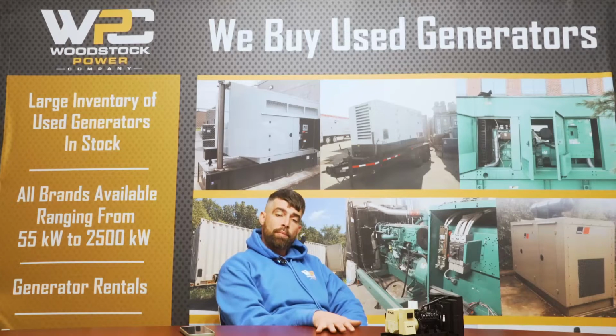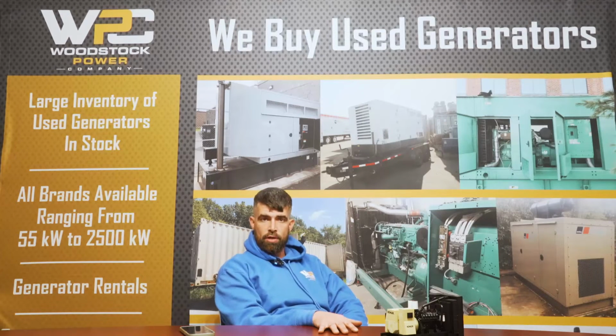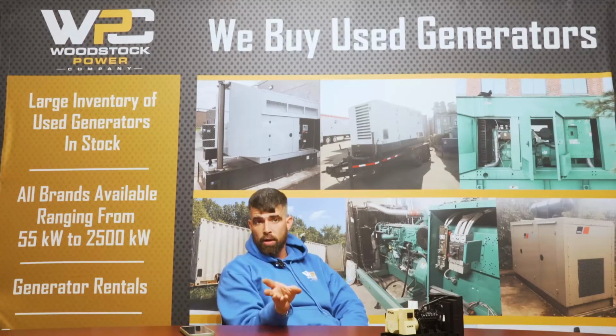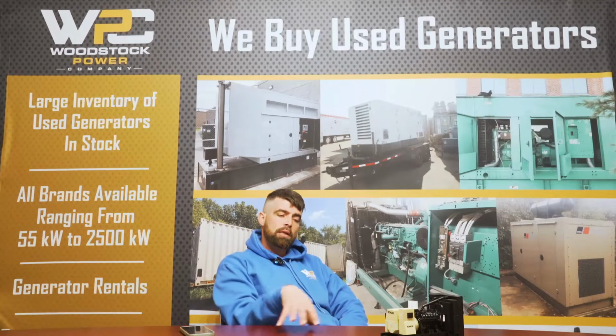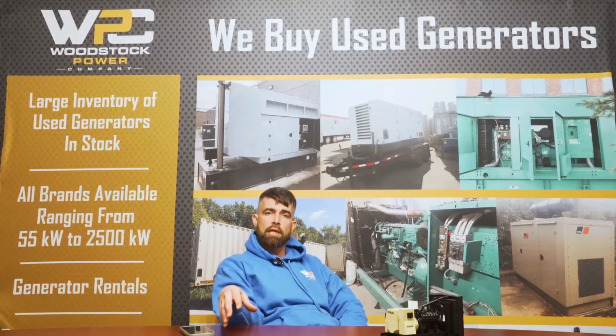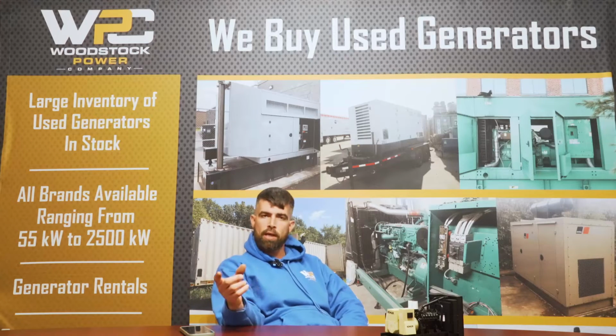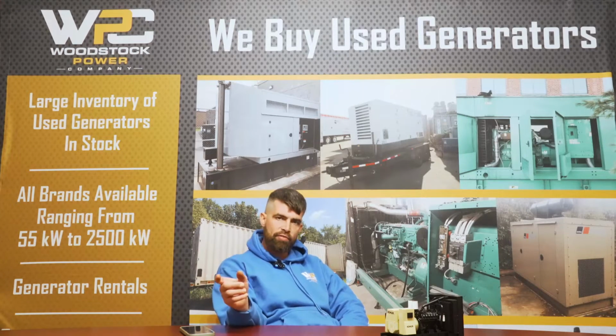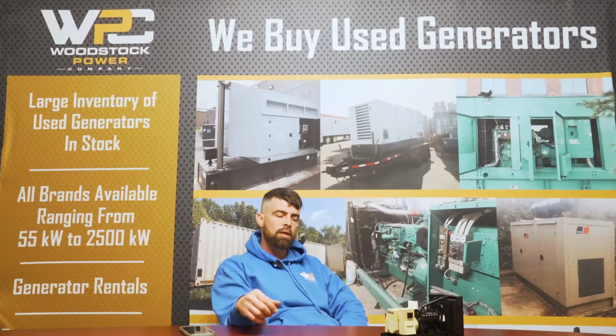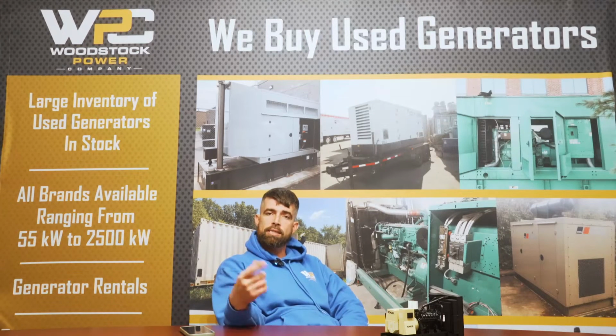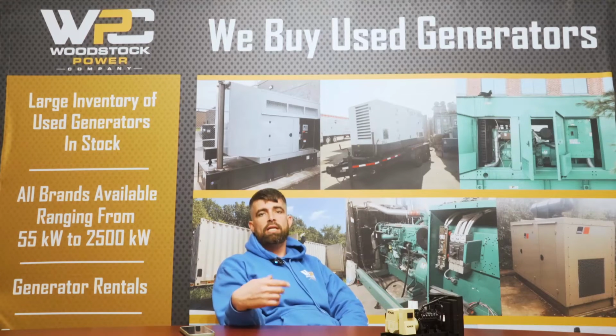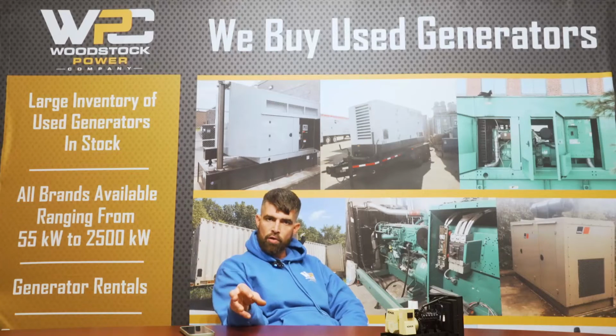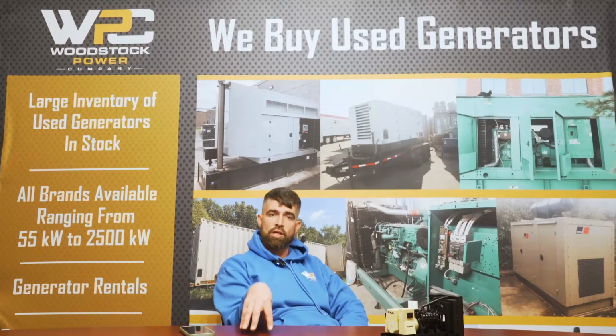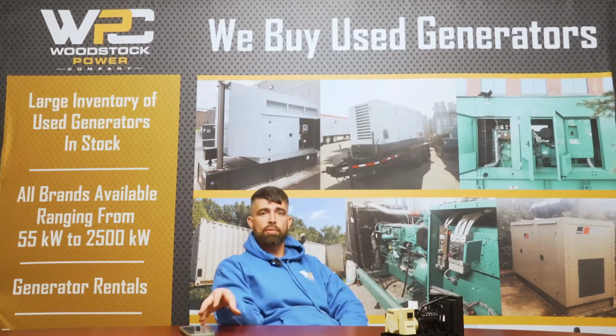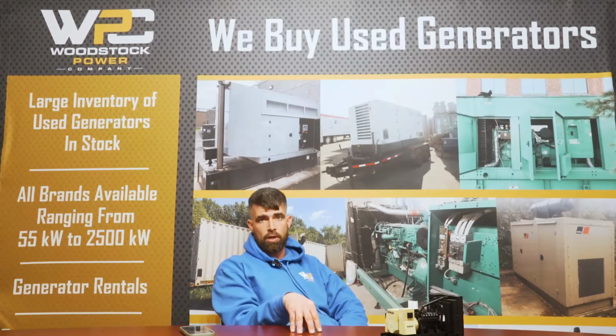So it is recommended that you run your generator at least once a week for about 20 to 40 minutes. A lot of the time, if you have your generator connected to your facility and it has a transfer switch, it's already programmed to run on a weekend or overnight at some point for about 30 to 45 minutes. Again, depends on the size and the location. But what that does, it cycles the fluids throughout the generator. It cycles the engine, it cycles the generator, it cycles the radiator, make sure that all the parts are working correctly, and make sure that if anything needs to be adjusted, anything needs to be known of, like the alarms, will come up during that time and not when you actually need the generator to run.